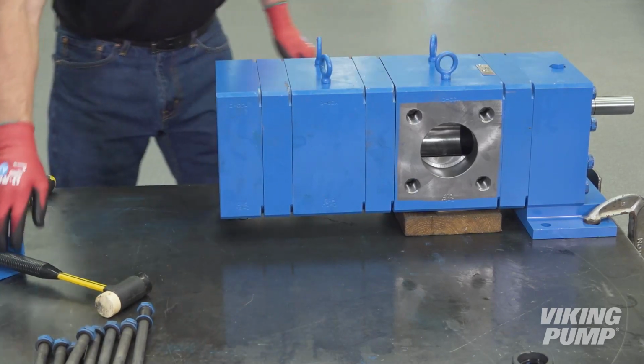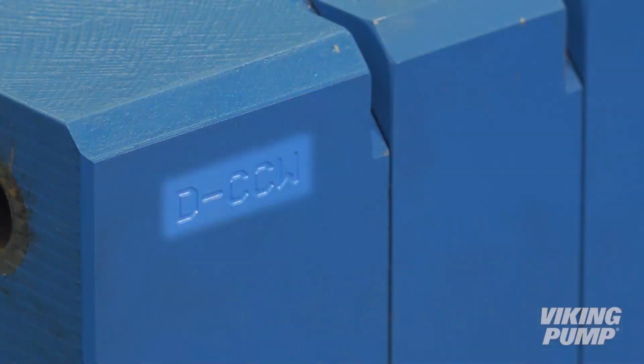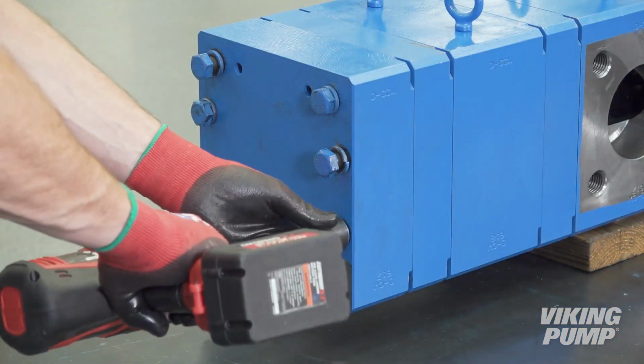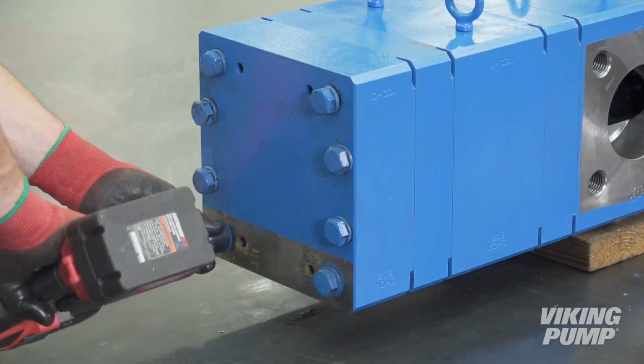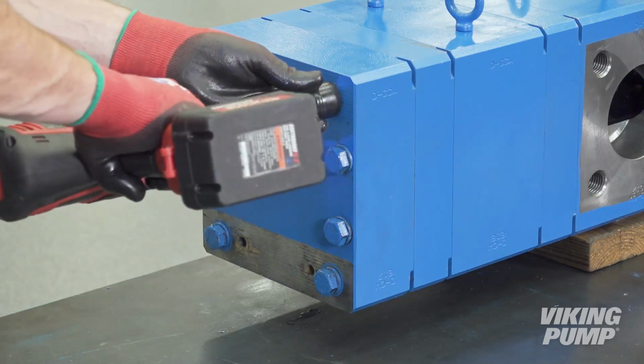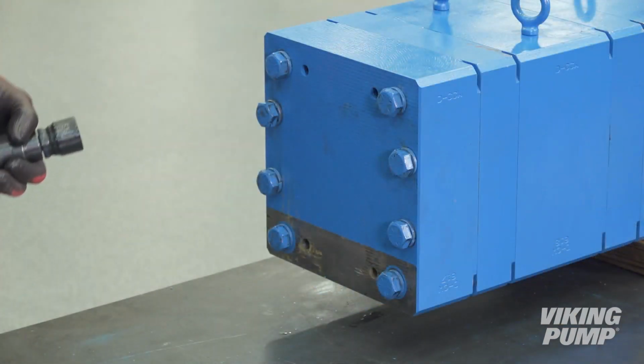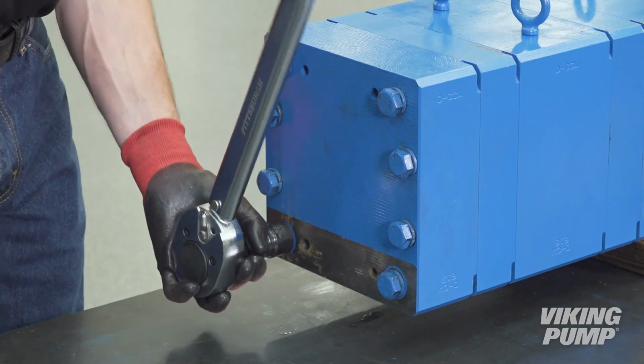To ensure that the pump is assembled correctly, make sure that the stamped characters are all on the same side of the pump. These can be found on the head, both separation plates, and the bracket. Install the head cap screws and tighten. Finally, torque all of the cap screws, both head and bracket.